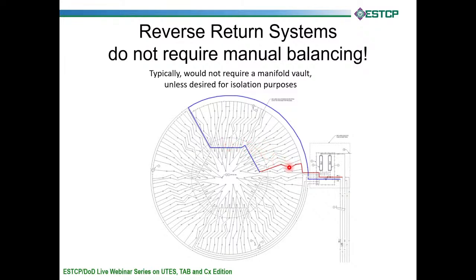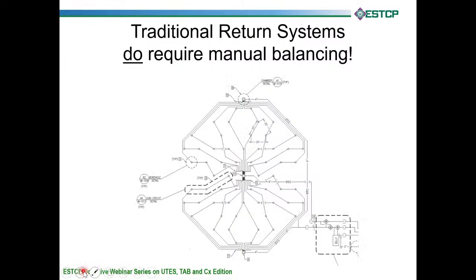We actually, on this project, took an ultrasonic flow meter while all of this was uncovered, and we measured the flow rate through each submain in all three trisectors and compared to the total flow of each trisector. And believe it or not, this actually works. Each of these submains were plus or minus 10%, I'm going to say, to be in the same flow rate. I'd always been told that they were self-balancing, but that was actually the proof in the pudding. And so we think this is a really good way to do it. Requires no manual balancing.